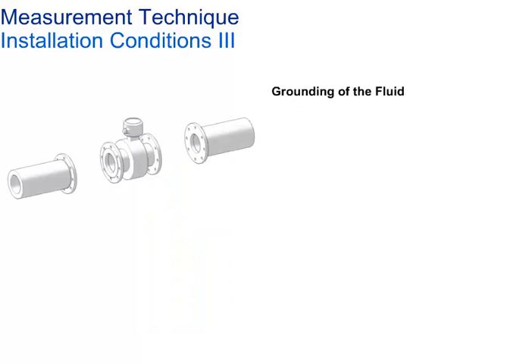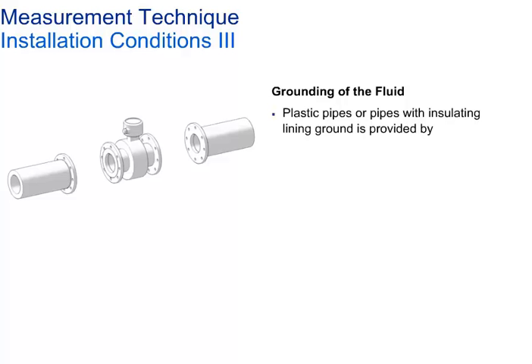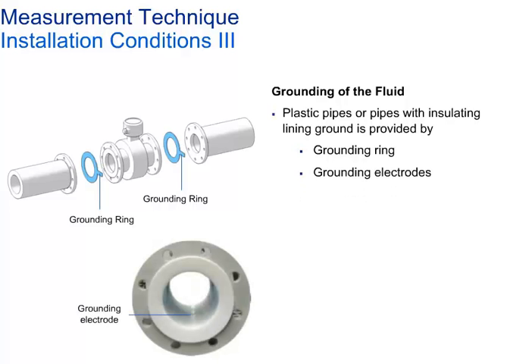Grounding is required not only for safety considerations but also to ensure proper operation of the flow meter. The signals measured at the electrodes are only a few millivolts in amplitude. With plastic pipes or pipes with insulating lining, the signal can be affected by stray ground currents flowing through the flow meter. To avoid this, the fluid must be grounded using grounding rings or grounding electrodes. When stray potentials are present, a grounding ring upstream and downstream of the flow meter sensor is required. The potentials in the station ground and in the pipeline should be identical, and a choice of grounding ring and electrode materials is available to ensure corrosion resistance.